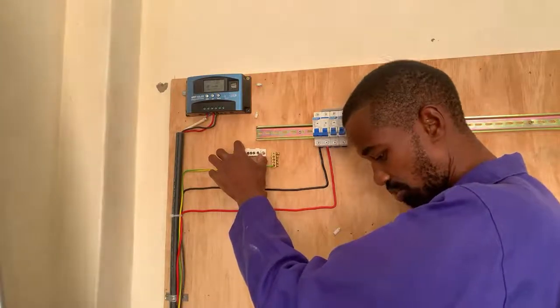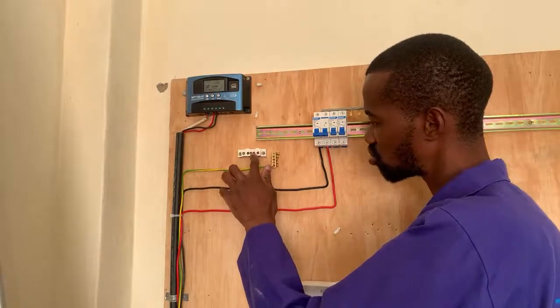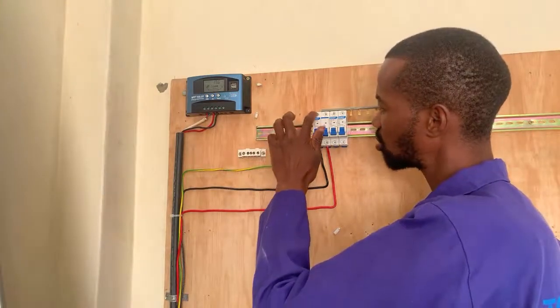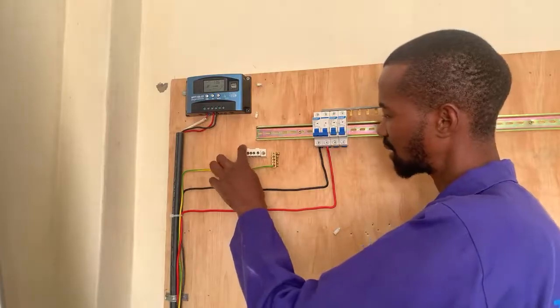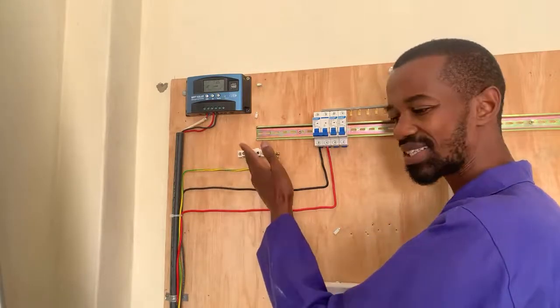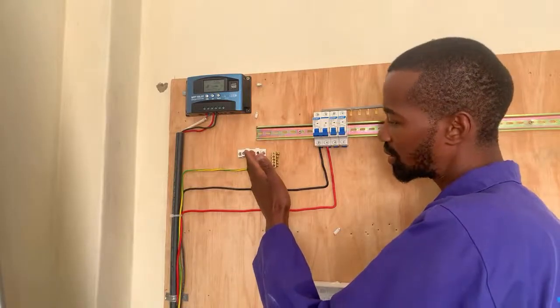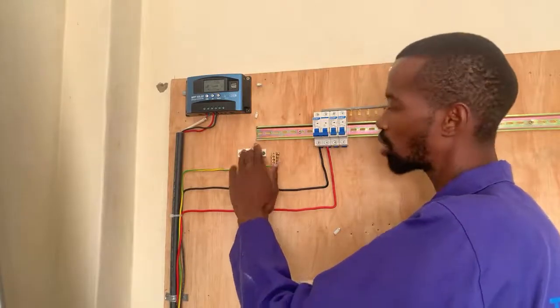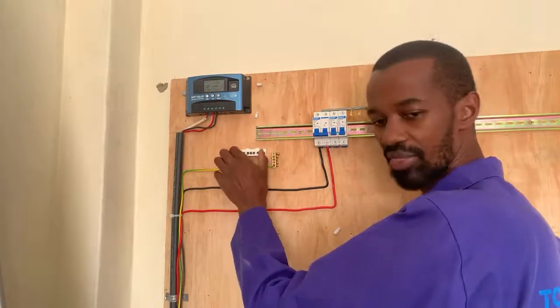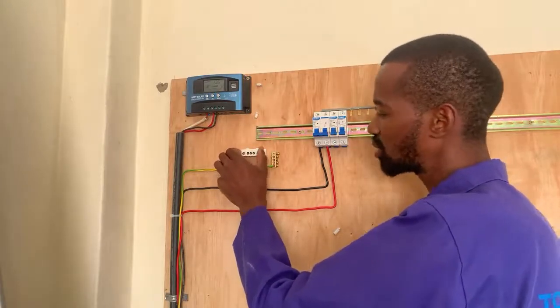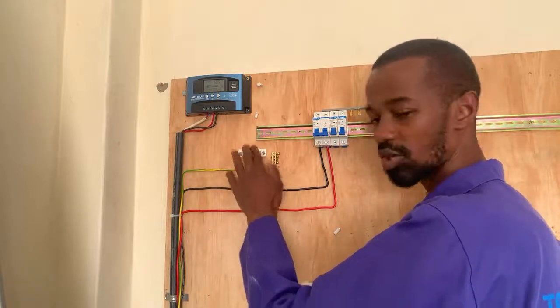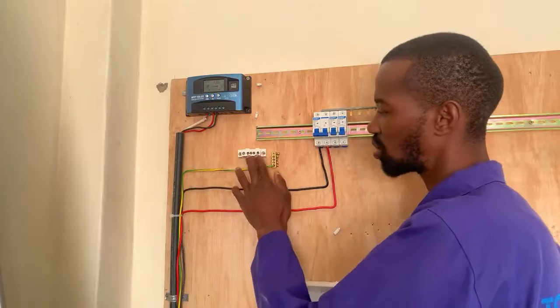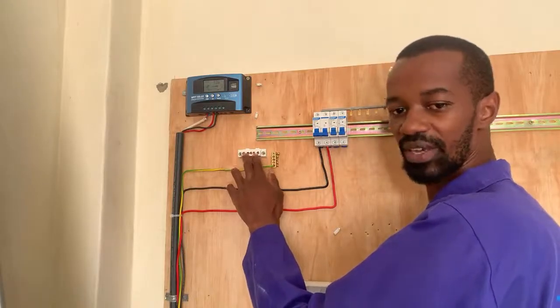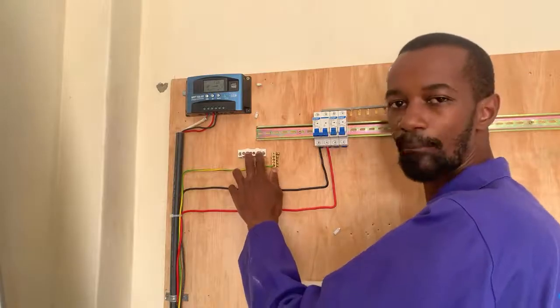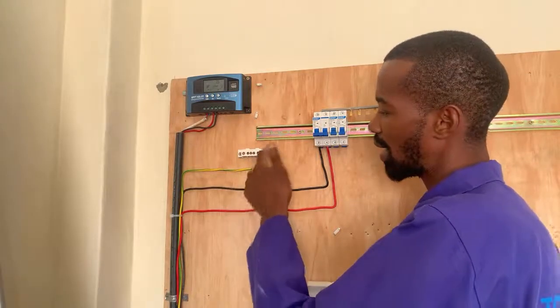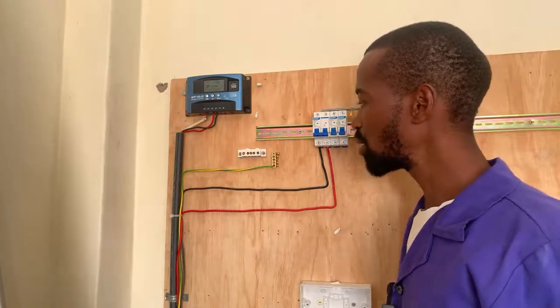Why am I saying so? Because in the consumer unit, we have this neutral bar. So we will take only a single cable from this particular point to this particular neutral bar, so that each and every circuit will tap its neutral from here, or it will have a return path through this neutral bar. And the good thing about the neutral bar is that it is made of pure copper. The screws and also the connection here will be very tight, meaning that we will have such a perfect electrical connection, and we will also have a good mechanical connection.